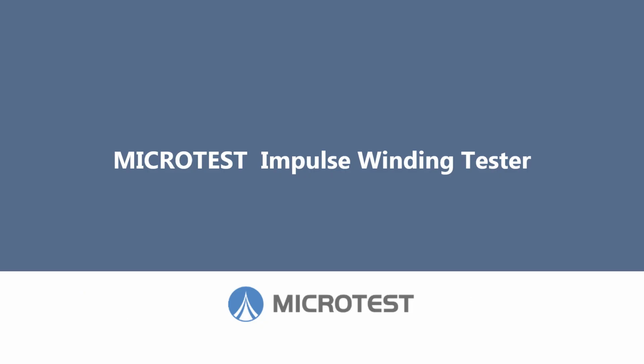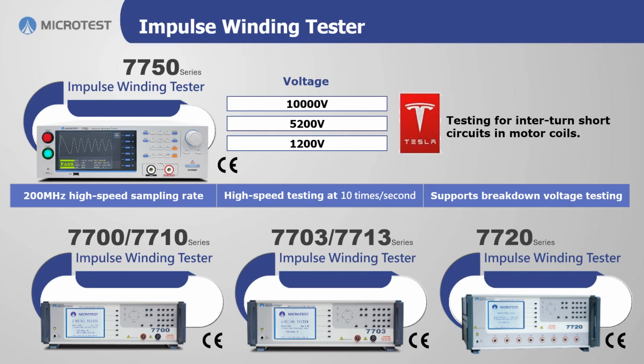Let's move to the impulse winding tester. The impulse winding tester is designed primarily for testing the insulation reliability of wound components in winding processes. The product line includes the latest generation 7750 series, the 7700 series, 7703 series, and the multi-channel 7720 series. In the latest 7750 impulse winding tester, the pulse voltage output capabilities are 10 kV, 5.2 kV, and 1.2 kV. It features a high sampling rate of 200 MHz, a highest testing speed of 10 times per second, and also supports breakdown voltage testing. The Microtest impulse testing has received acclaim from major US electric vehicle manufacturers and has been widely adopted in testing applications.